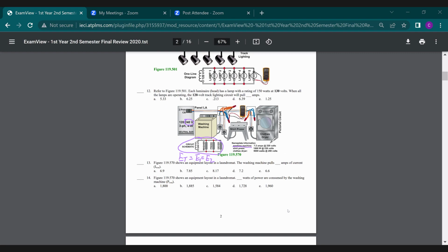All right, the nameplate is 220, so we have to find resistance no matter what. We have amps, we have volts. R is equal to volts divided by amps. So if I take 220 divided by 7.2, this will give me that resistance there. Then I can use that resistance and my actual applied voltage to answer my 2 questions. 220 divided by 7.2, I got 30.5 repeating. So we'll go 30.56. That's ohms.